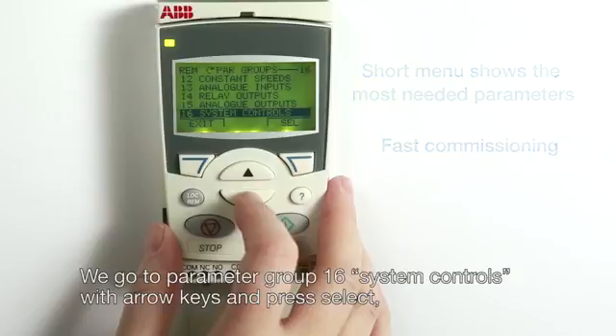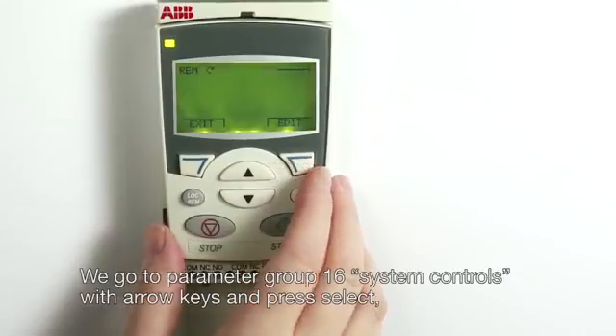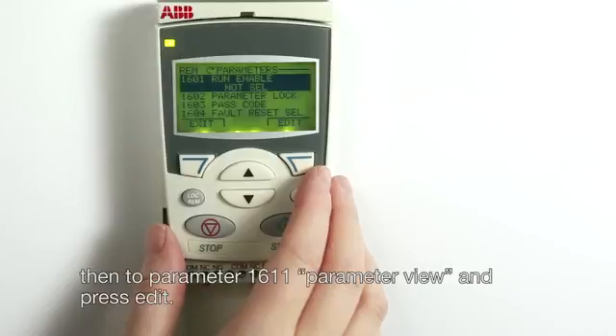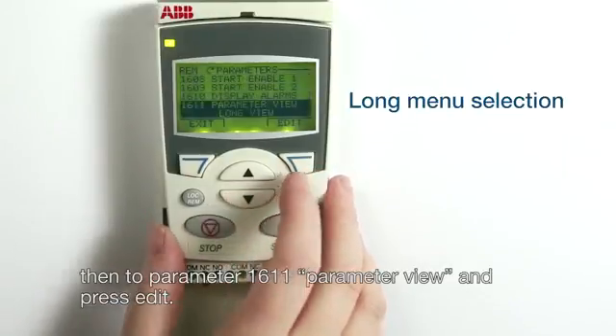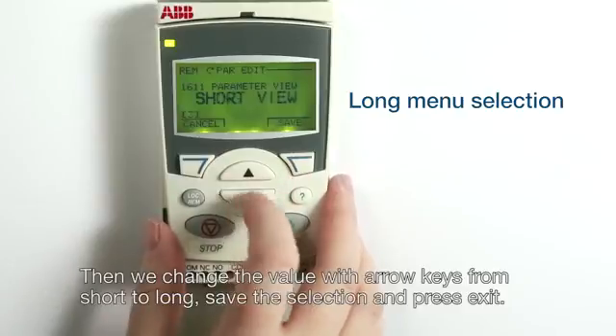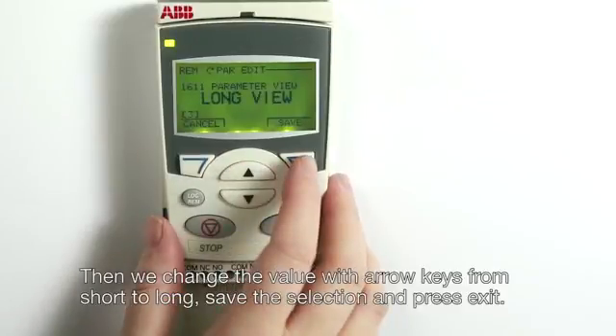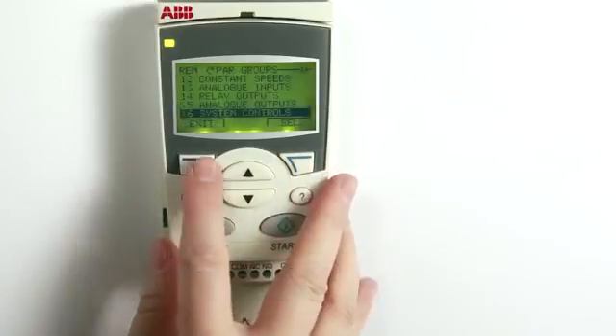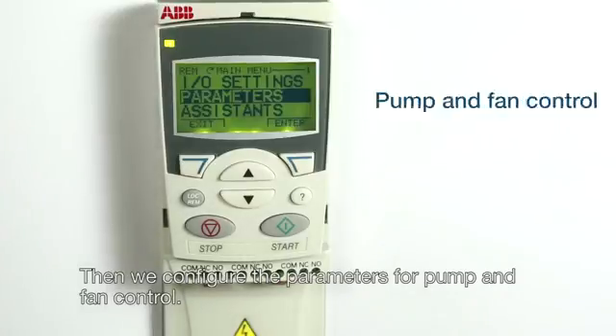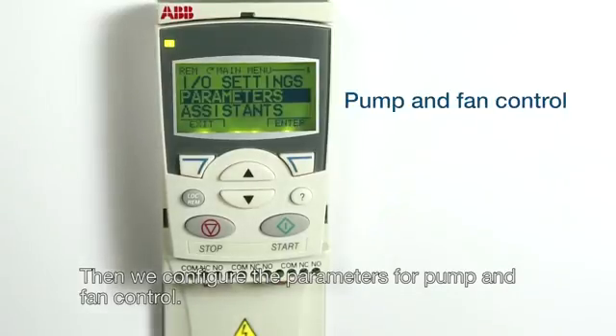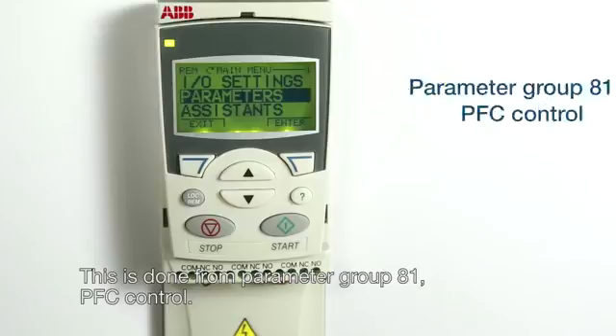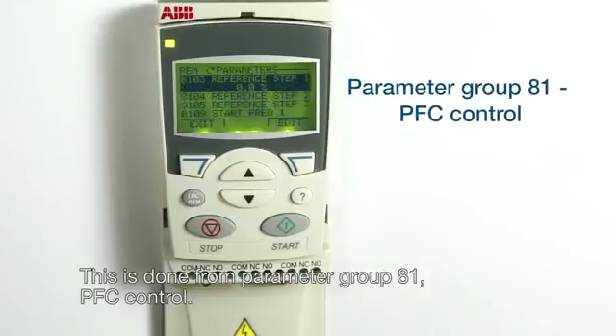We go to parameter group 16, System Controls, with arrow keys and press Select. Then to parameter 1611, Parameter View, and press Edit. Then we change the value with arrow keys from short to long. Save the selection and press Exit. Then we configure the parameters for pump and fan control. This is done from parameter group 81, PFC Control.